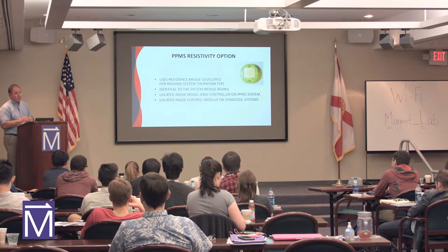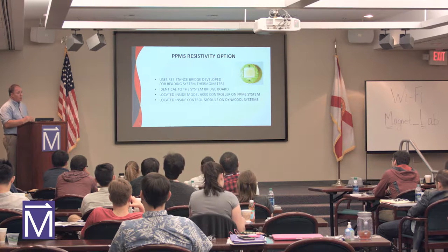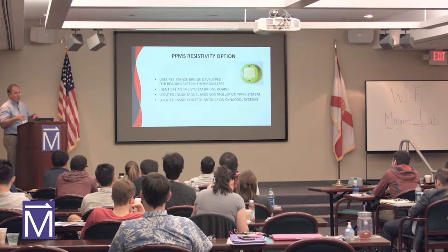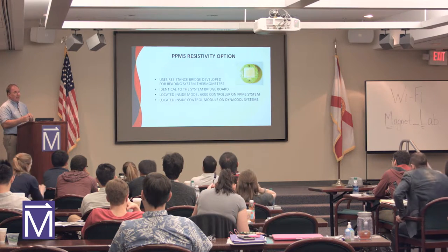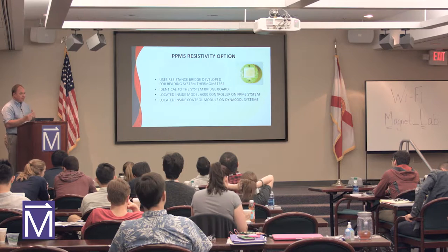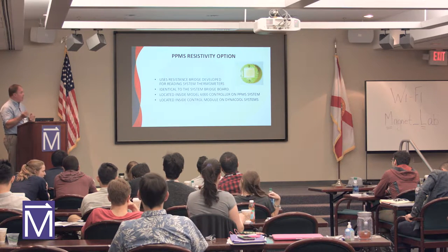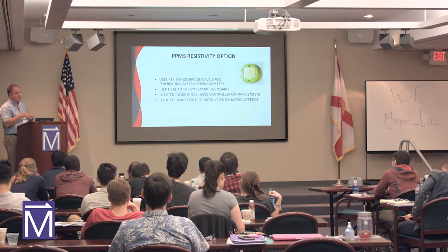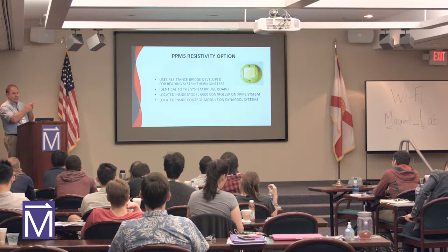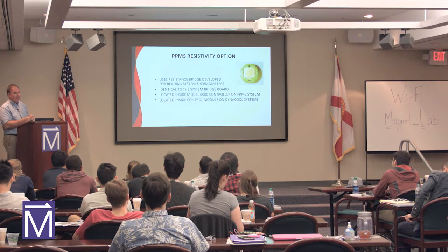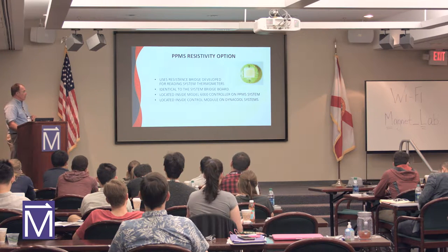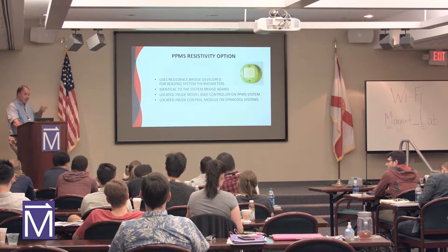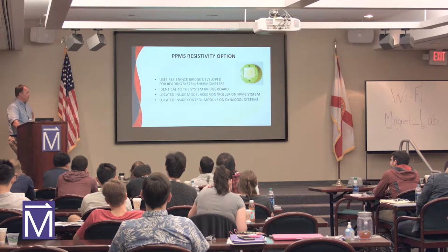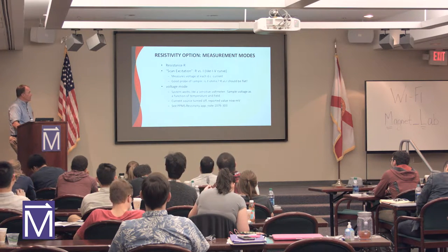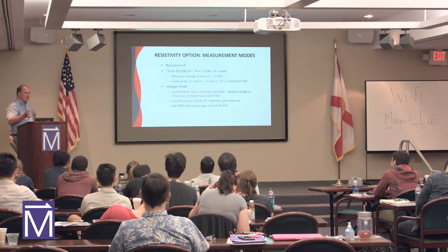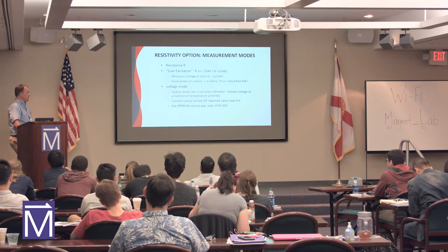The resistivity option that we built in uses the bridge that we developed to read the thermometers on all the systems. So we have thermometry in the sample chamber in proximity to the sample. On the PPMS in the lab, it's part of the model 6000 controller. In the Dynacool system, it's in the control module. So it's a little subtlety in the electronics, where the electronics location is.